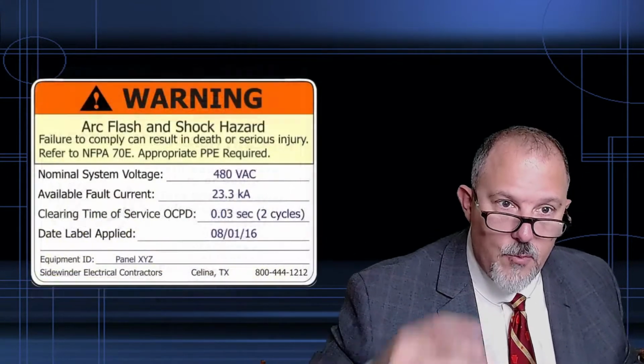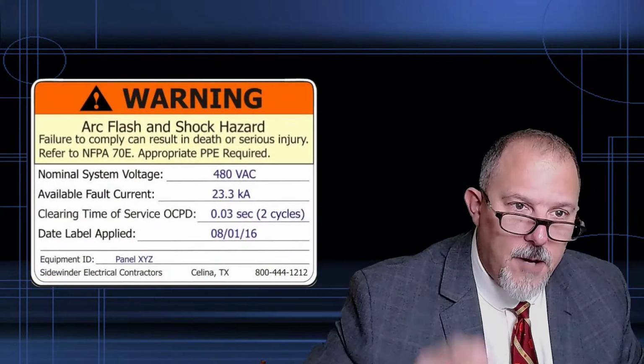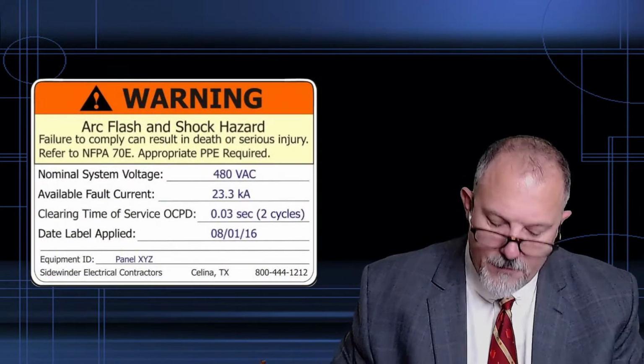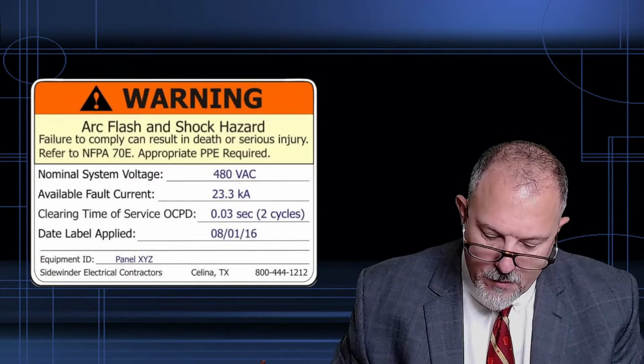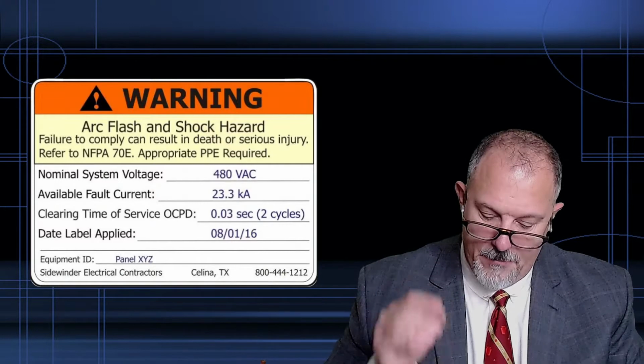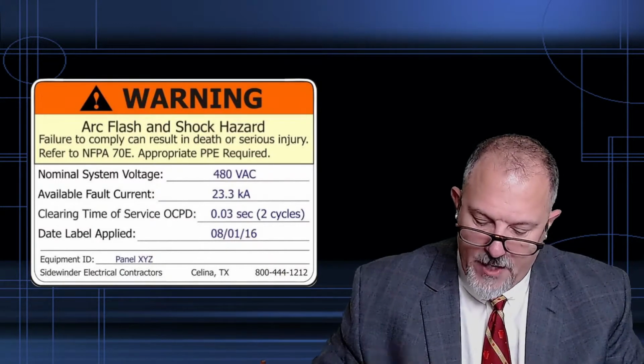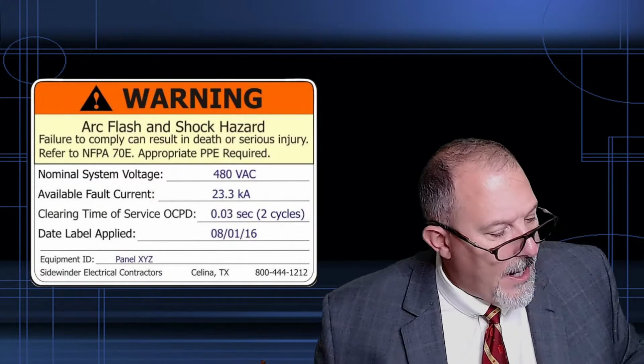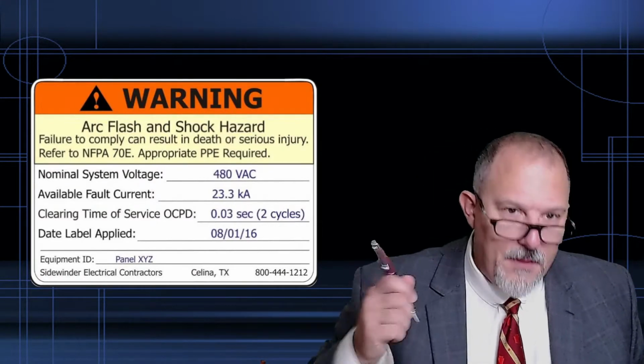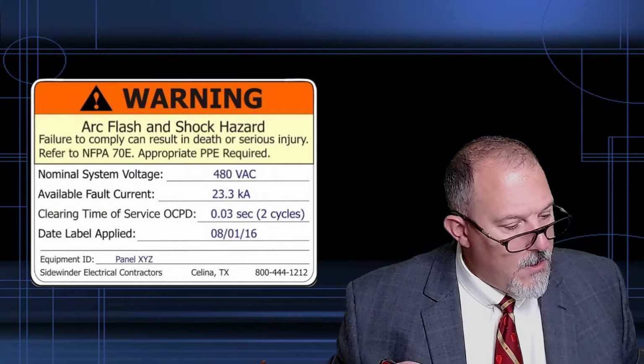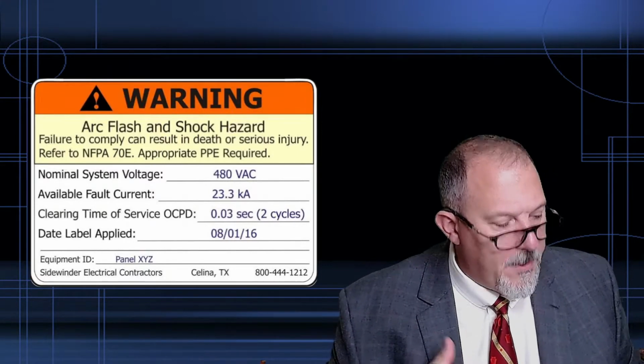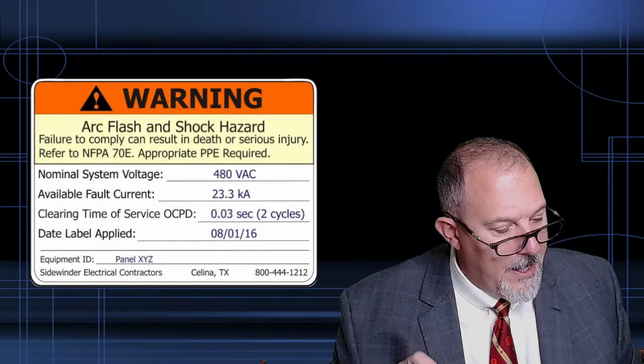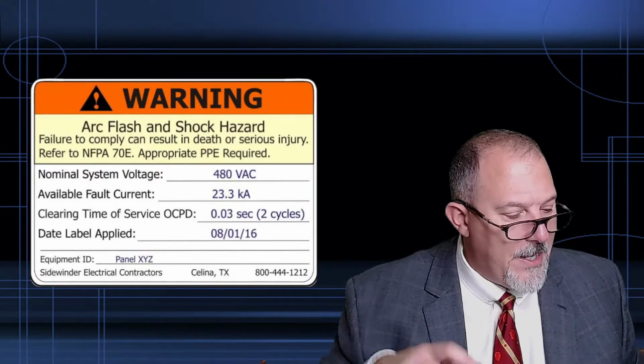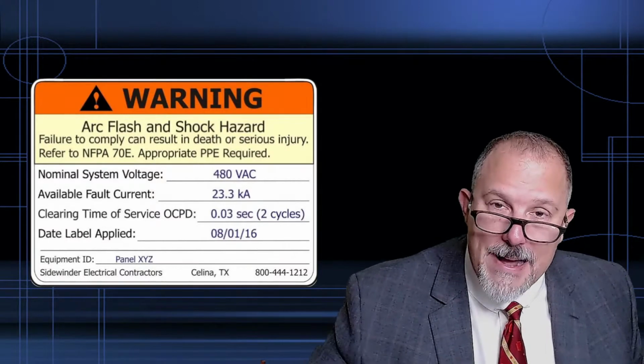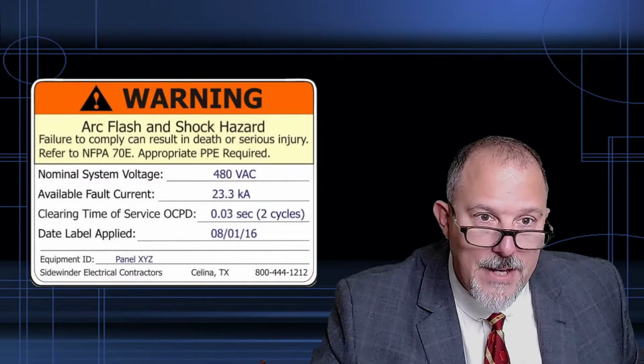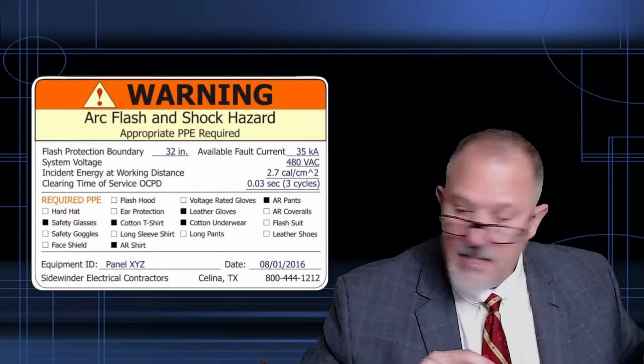But in the 2017 code, we introduced the nominal system voltage. You have to put in nominal system voltage, available fault current at the service overcurrent protective devices, the clearing time of the service overcurrent protective devices based on the available fault current at the service equipment, and then the date the label was applied. And this is what your label will look like. Now, there are a few informational notes. There's an exception: service equipment labeling shall not be required if an arc flash label is applied in accordance with acceptable industry practice. Which one? What's that one? That is this label. This is the 70E label.